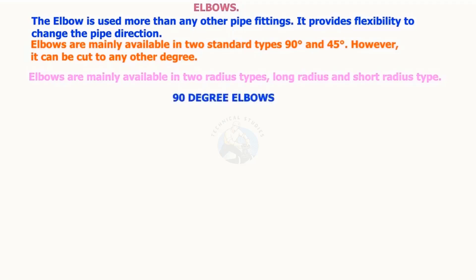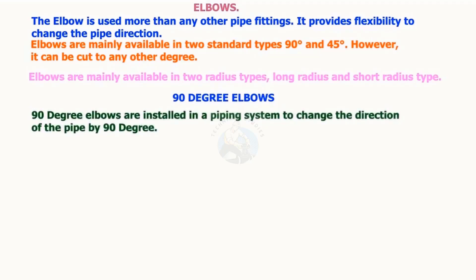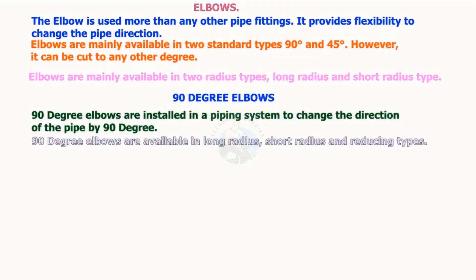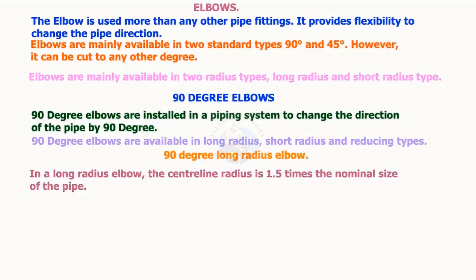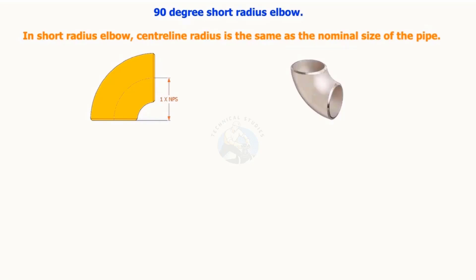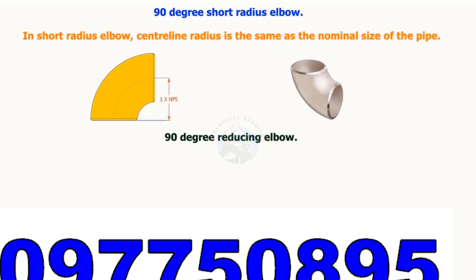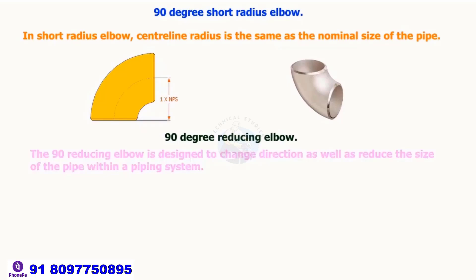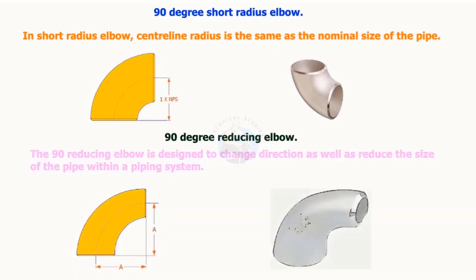90-degree elbows are installed in a piping system to change the direction of the pipe by 90 degrees. 90-degree elbows are available in long radius, short radius, and reducing types. In a long radius elbow, the centerline radius is 1.5 times the nominal size of the pipe. The 90-degree reducing elbow is designed to change direction as well as reduce the size of the pipe within a piping system.